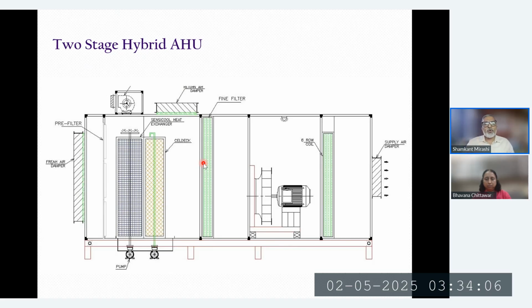I should take the air, filter it appropriately, and just put it in the space. If I have air at, say, 35-40 degrees with humidity just about 20%, which is very common in Pune, that means I can get 22 degrees at supply. Why should I run my refrigeration? I can take that air, cool it with two stages of cooling, and offer it in the space.